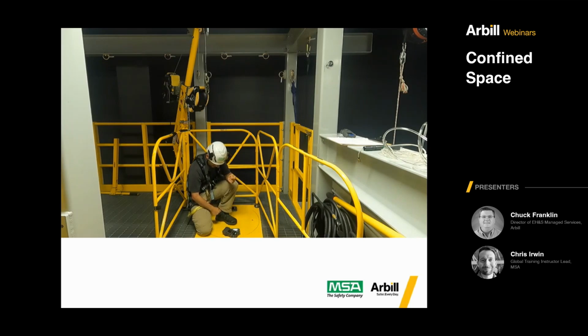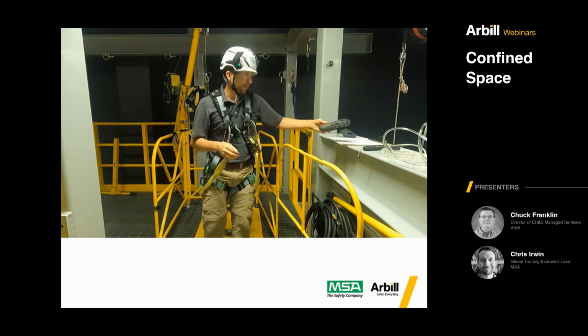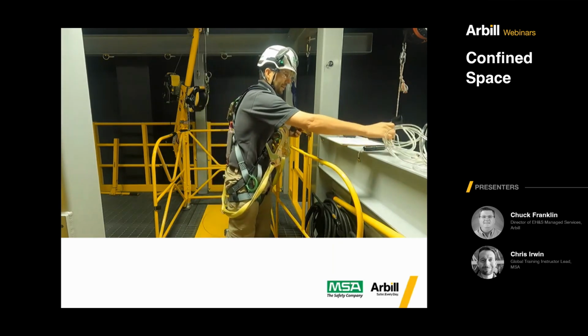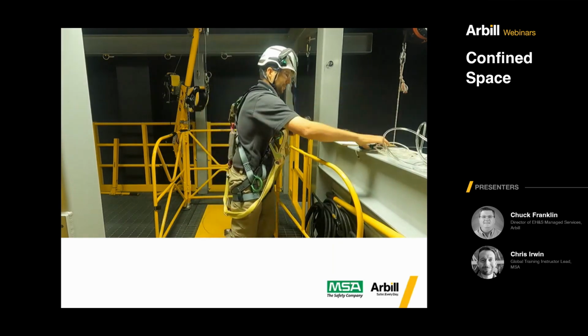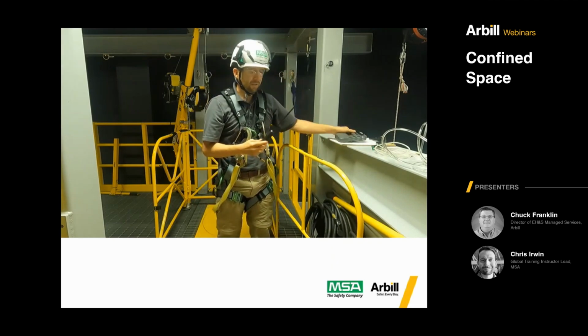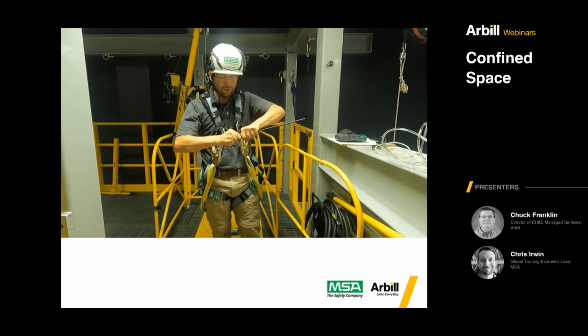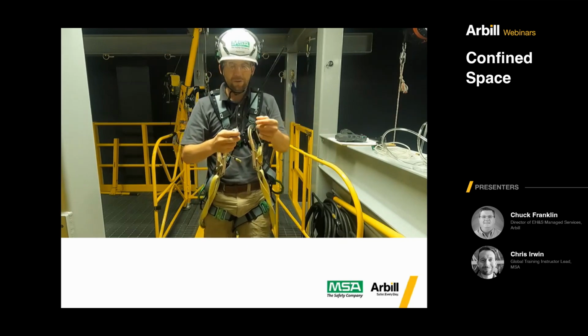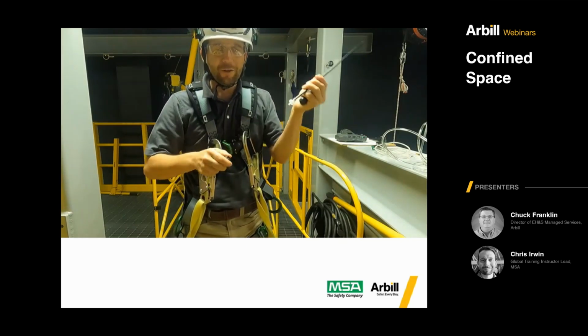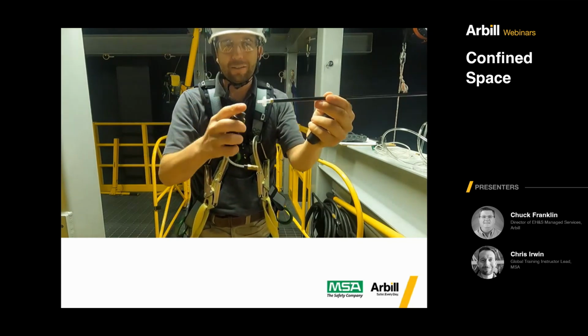Right now, my gas detector is reading 0 for everything except for the oxygen, which is at 20.8, which is the standard atmospheric air reading that MSA has on the gas detector. So at this point, I'm going to go ahead and start getting ready to test the atmosphere inside. The first thing I'd like to quickly show is the probe that's going to go on the end of the line for the 5X.